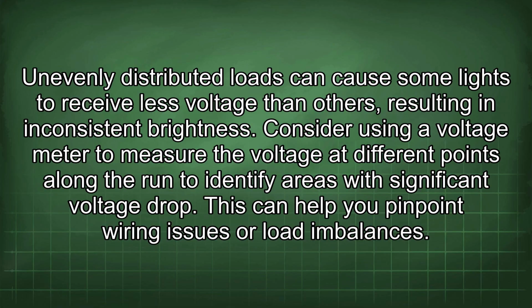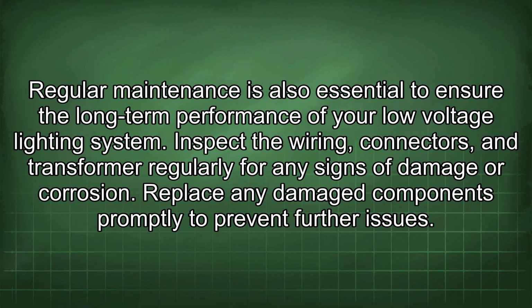Consider using a voltage meter to measure the voltage at different points along the run to identify areas with significant voltage drop. This can help you pinpoint wiring issues or load imbalances. Regular maintenance is also essential to ensure the long-term performance of your low-voltage lighting system. Inspect the wiring, connectors, and transformer regularly for any signs of damage or corrosion. Replace any damaged components promptly to prevent further issues.